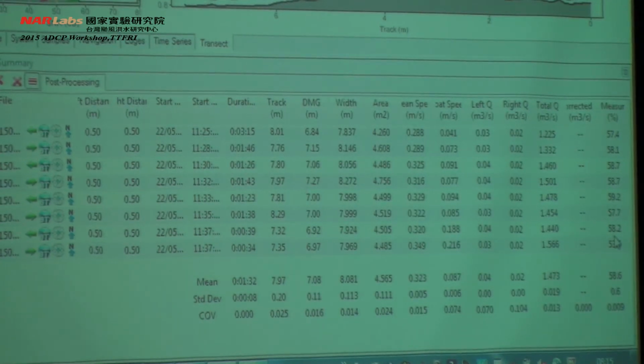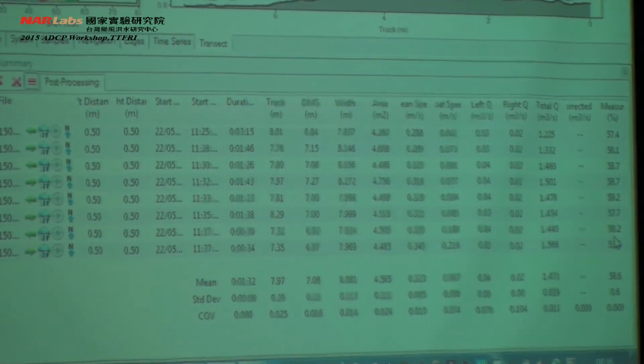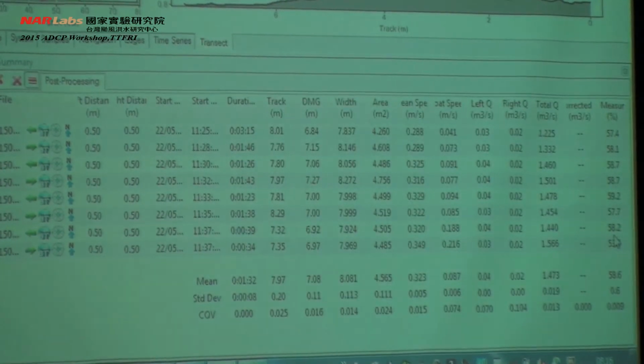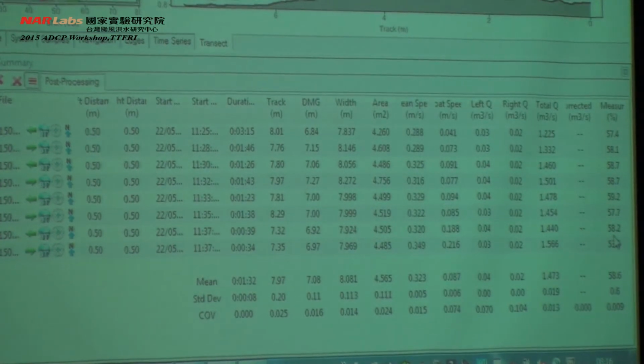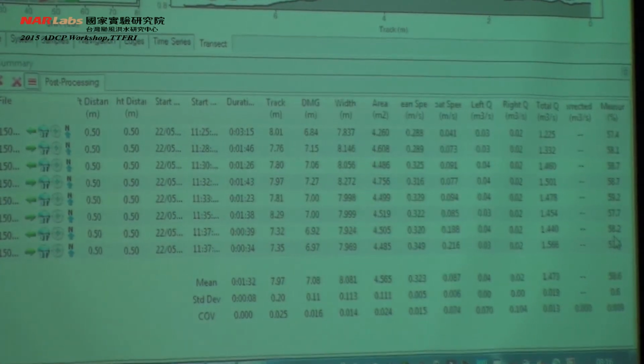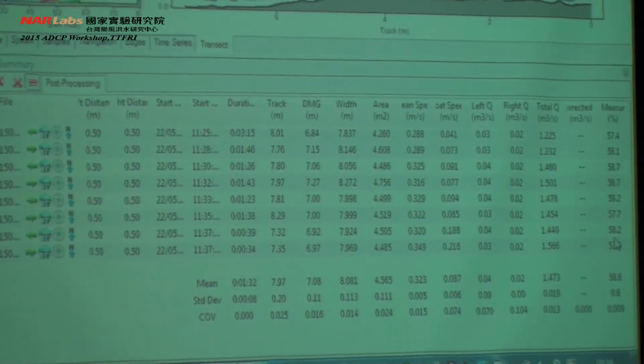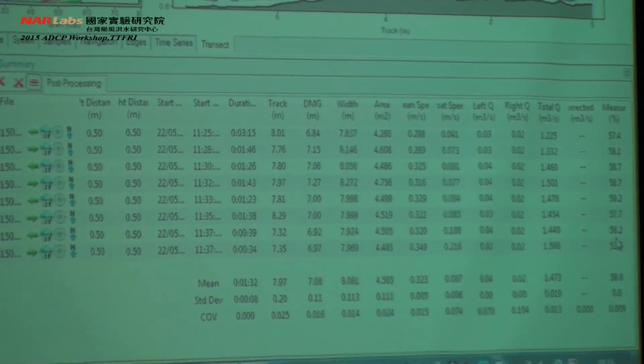If you think about a mechanical meter, you'd probably be measuring, in that same situation, something like 10 to 15% of the channel. And we accept that. So we've massively increased the amount we are measuring. I've seen good data down as low as 30, 35%. Would I always trust it? No. I think once you get below 50%, I would start to look for a different site.